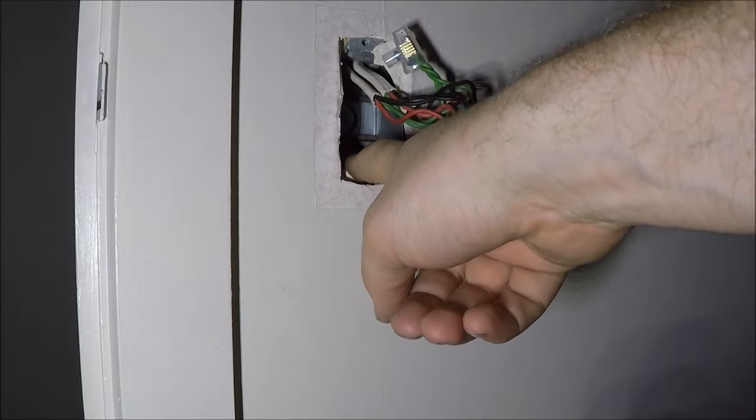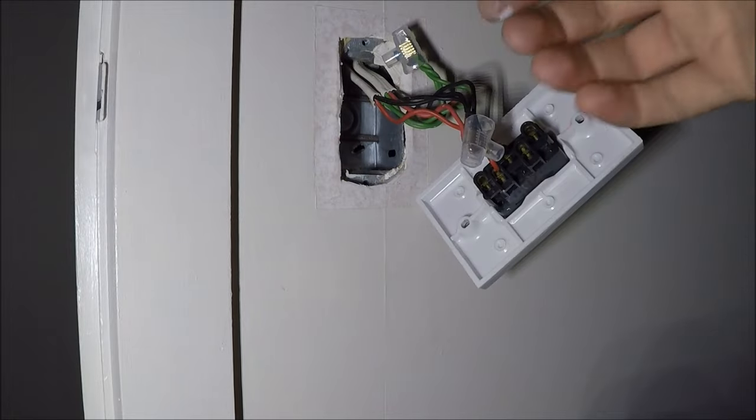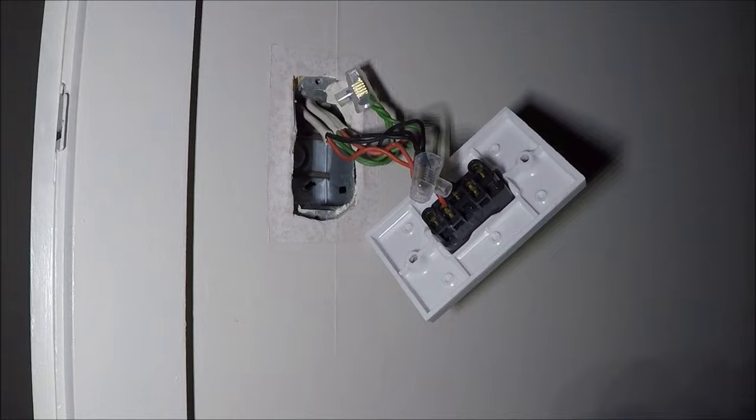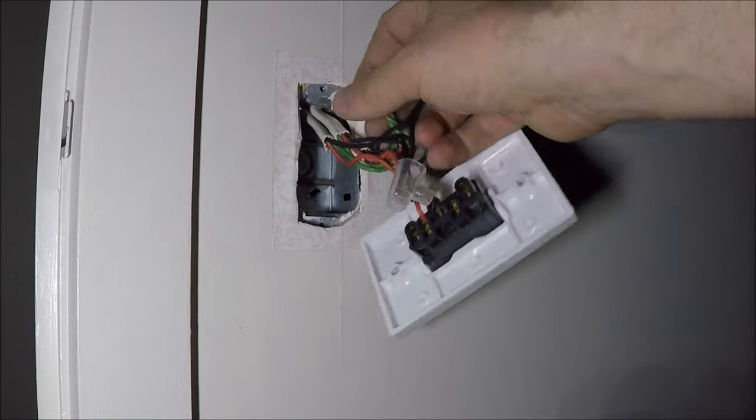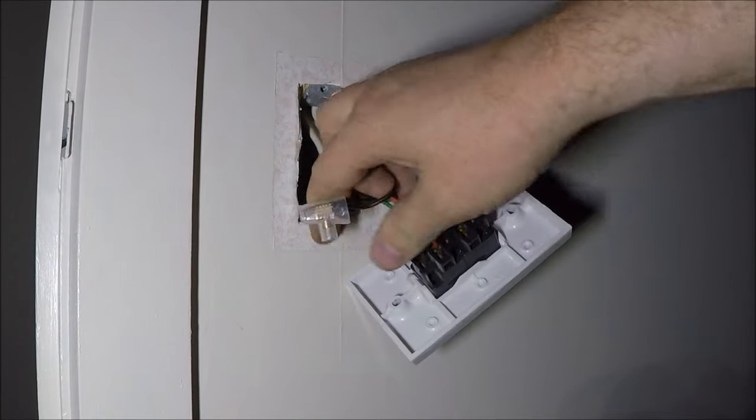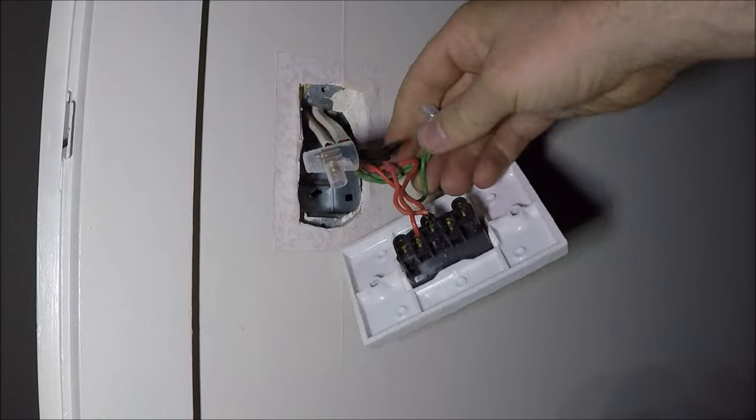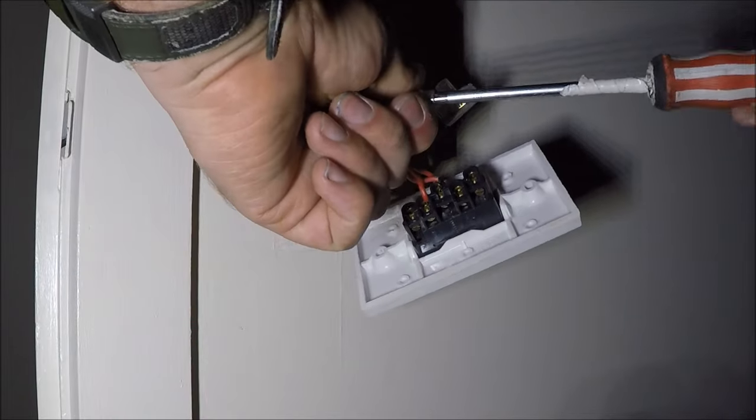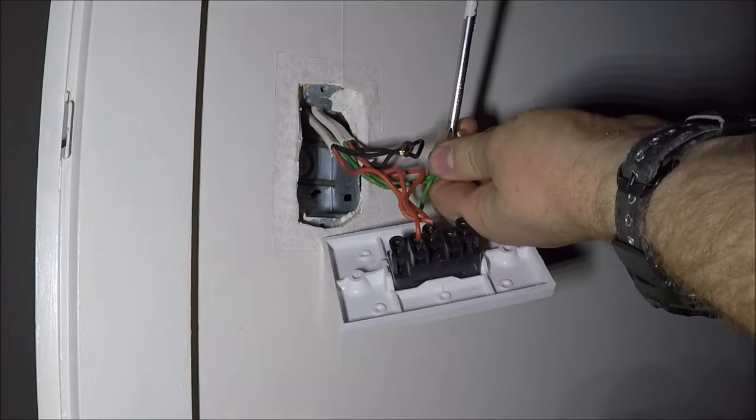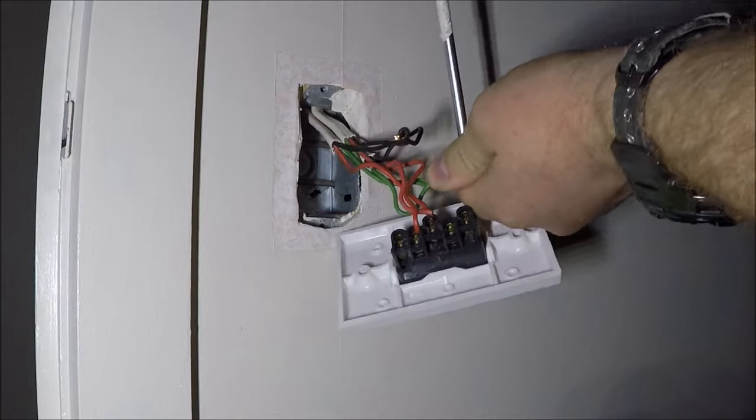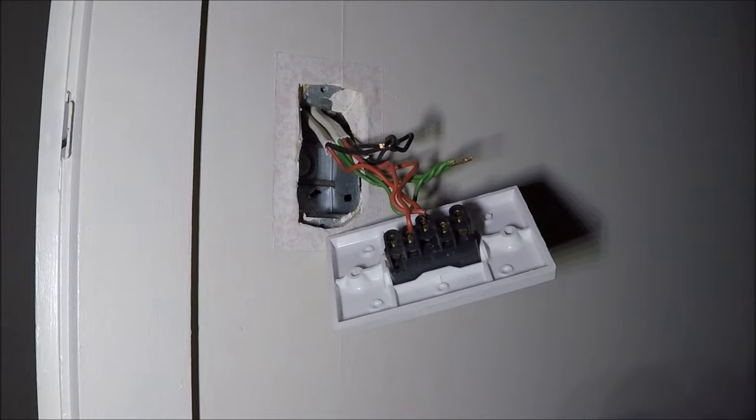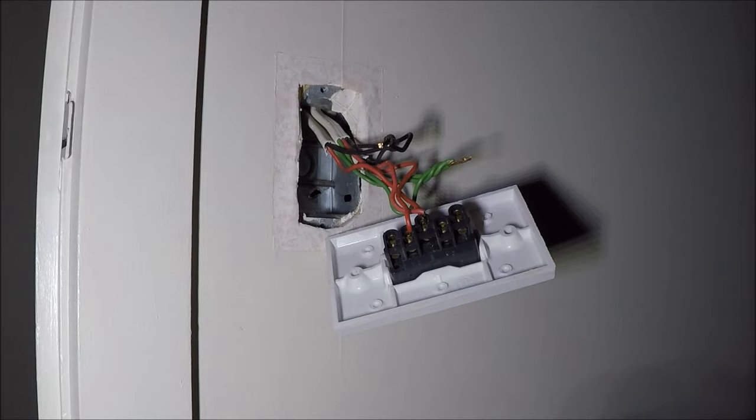Bugger. Always check the box in behind. This box here, I'll be ripping out and replacing, and I'll be putting a new plastic one in, which will mean I'll have to take these bloody connectors off I've just thrown on. The only reason I'm taking them off is fittings don't fit in them properly. If it's a single switch, it'll fit in there all right, but if you're going any bigger, I'd suggest ripping it out, throwing in a new plastic one.